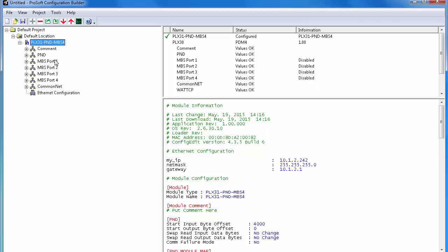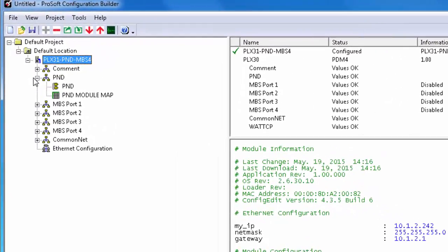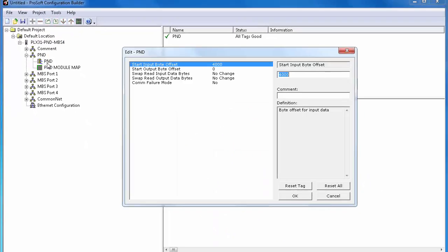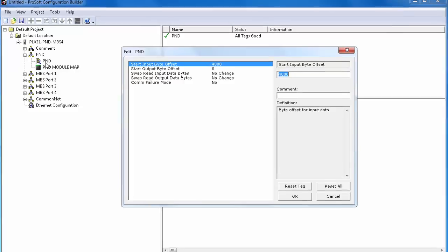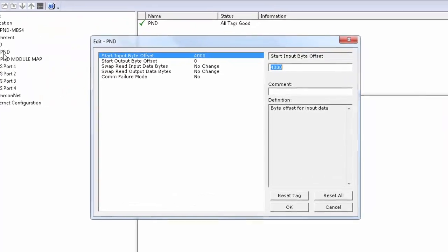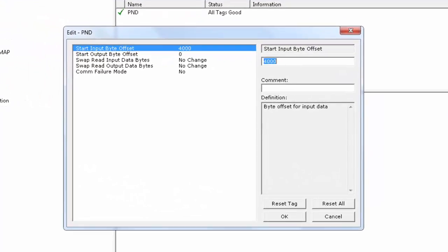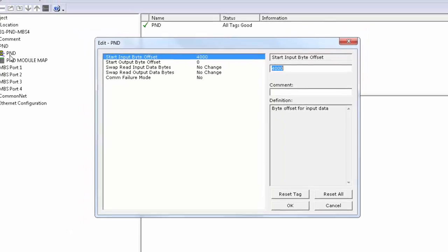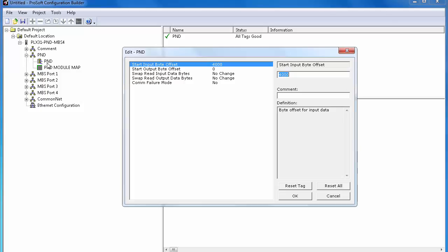Now, make sure that the IP address is in the Ethernet field and choose Download to permanently set the IP address. With that done, we can configure the PROFINET portion of the gateway. The first section, PND, is configuring the PROFINET device port, and the second, PND Module Map, is configuring how much data will be exchanged between the module and the PROFINET controller. We'll also map in some status data that will alert the controller if communication with the Modbus devices are lost. Begin by clicking on PND.